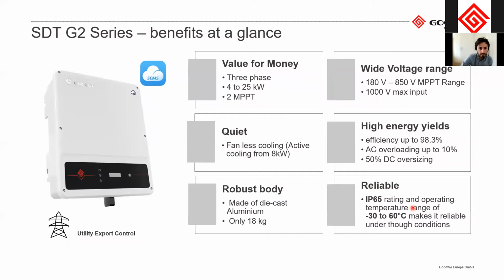Going to our SDT G2 inverter. As I said, this is our only 3-phase inverter for residential applications. It goes from 4 up to 25 kilowatt. It has 2 MPPTs, also has a wide voltage range and much higher input voltage compared to the single phase inverters, of course. So it has between 180 up to 850 volts of the MPPT range.